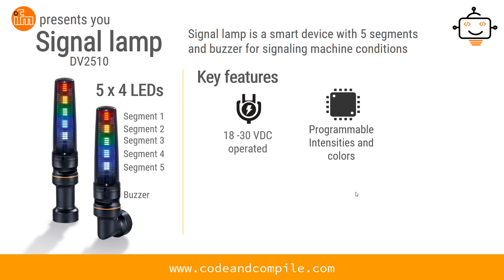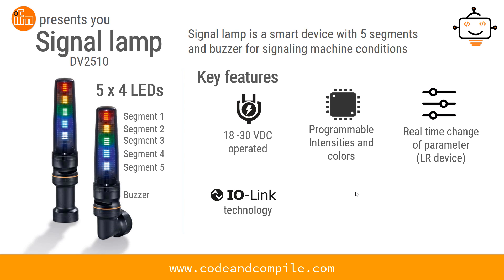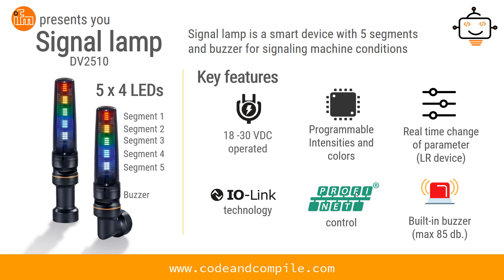The key features of this device are: it operates on DC voltage ranging from 18 to 30 volts; it is programmable — you can program various colors, intensities, and the buzzer; it supports real-time parameter changes using an LR device; it supports high-speed IO-Link technology to link directly to available ports; it supports PROFINET for read/write with a PLC; and it has a built-in buzzer with a maximum 85 dB audible range.